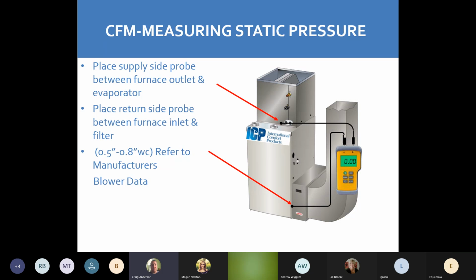You're going to get there, that motor's going to turn on, everything's going to be hunky-dory, you think, if you haven't checked that static pressure. Typical static pressure for a system is 0.5 to 0.8. This is the range we like. If we're too high, then our motor is working too hard, and then we can be looking at failed motors on a unit on a yearly basis or something to look at.